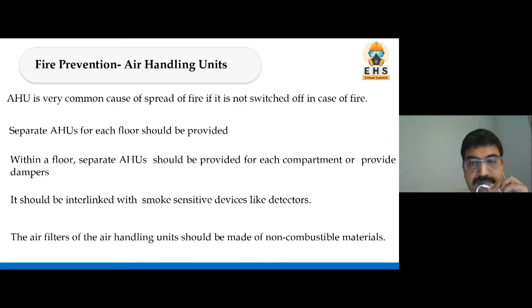Then it should be interlocked with smoke sensitive devices like detectors. How will we come to know that there is a fire? So normally there are fire detectors, smoke detectors. Similarly for the air handling units, we provide these dampers, but how will those dampers activate? Those get activated because they are interlinked with these detectors. And as far as other accessories of air handling units are concerned, for example, air filters, those should be of non-combustible material.